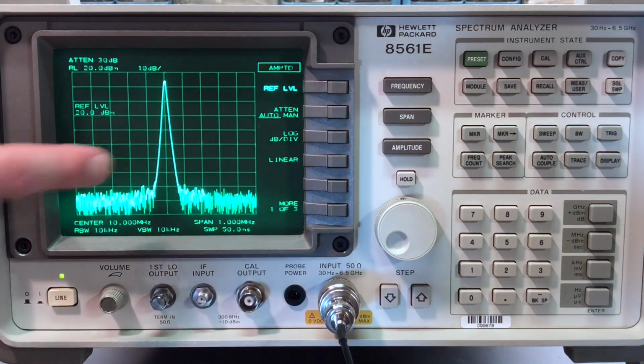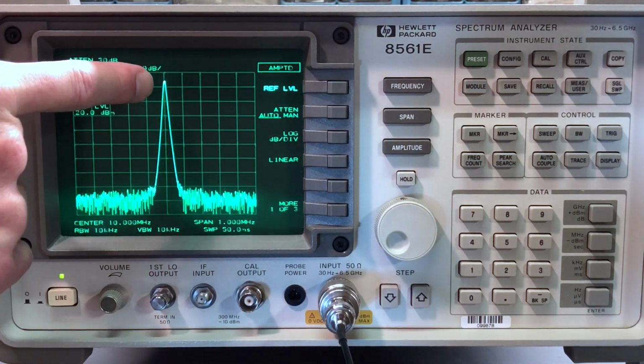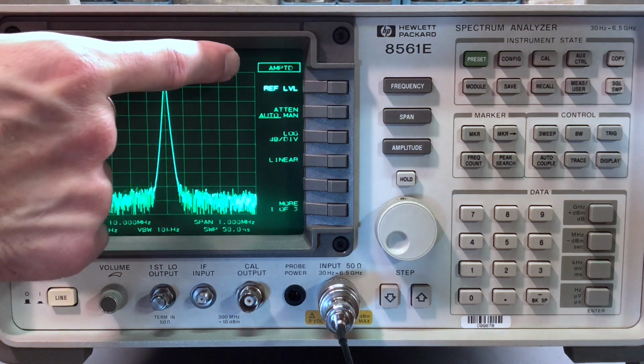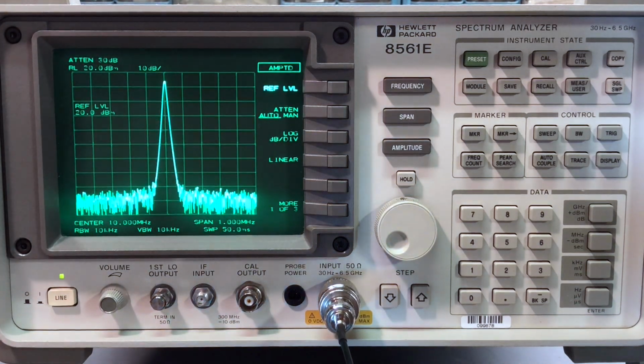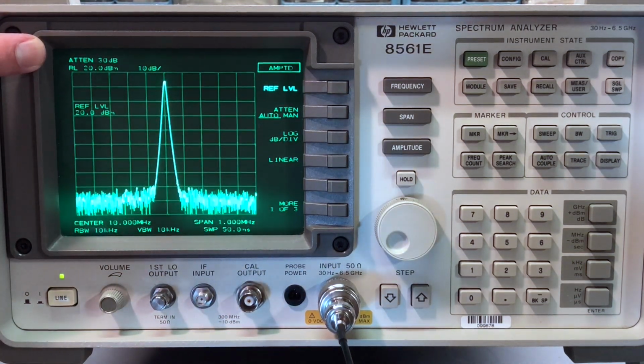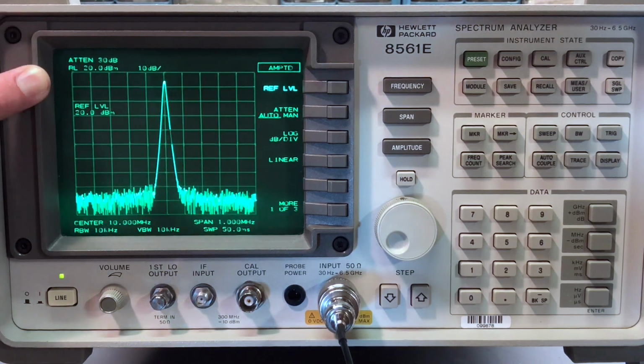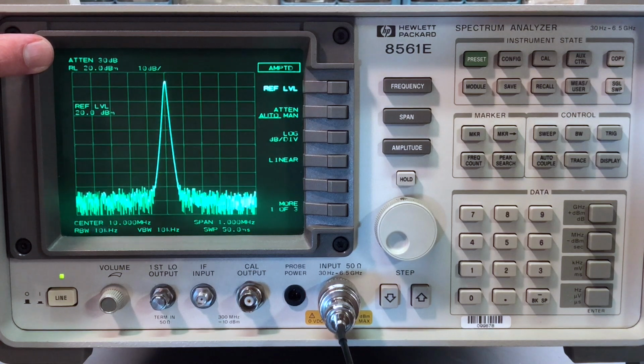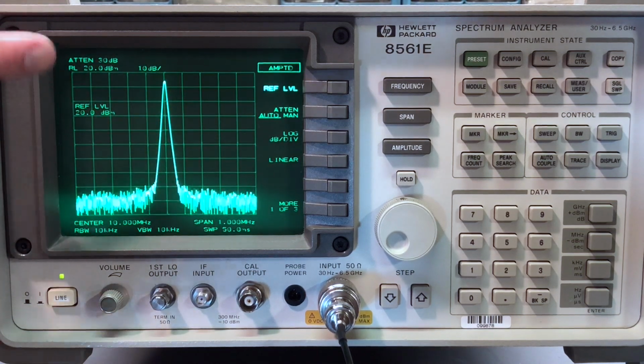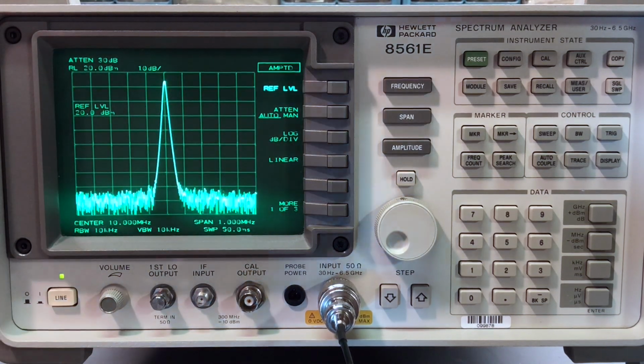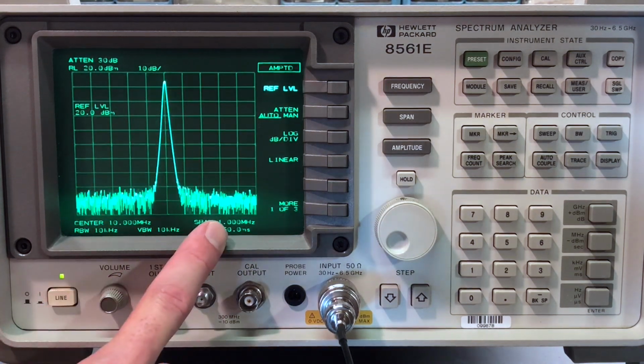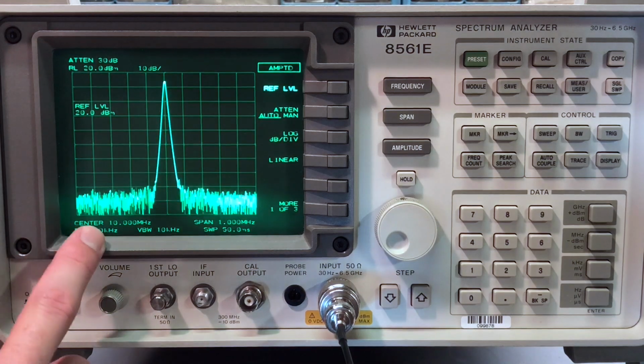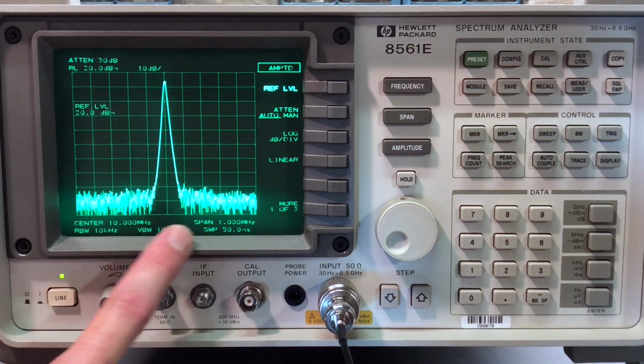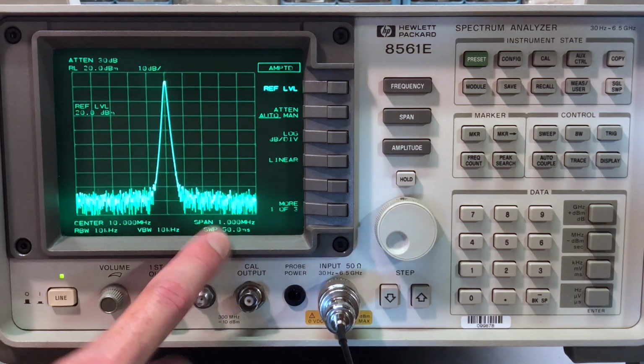Now ideally the amplitude on the peak of the signal that you're measuring, you want that to basically touch or be very, very close to the top graticule, which is the reference line. So right now you can see the reference line is at 20 dBm. You can see the attenuator is set at 30 dB. And this represents 10 dB per division on this scale vertically right here. Okay? So right now you can see the center is at 10 megahertz and the span 1 megahertz. Resolution bandwidth is 10 kilohertz, video bandwidth 10 kilohertz, and the sweep time is 50 milliseconds.